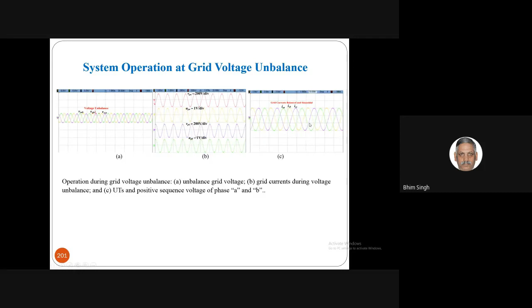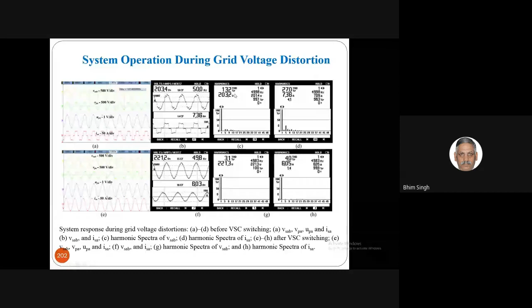So when voltages are unbalanced or distorted, it is still able to work, because we have to filter the voltage, but grid currents are maintained sinusoidal, balanced and in phase with the voltage, even with unbalanced voltage. So all those features we are able to take care of. And you can see how much the voltage is distorted, but the current is quite sinusoidal in that case.